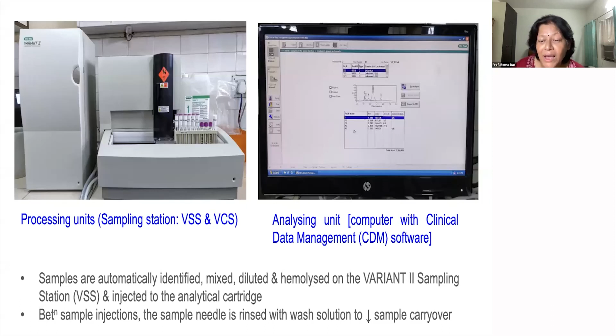Now, what are the guidelines for the interpretation of the results? You have to observe the following guidelines to assure acceptable results. The Variant 2 must pass calibration, and I'll show you the picture of how calibration looks. The retention time for the hemoglobin A2 in the calibrator is between 3.65 plus minus 0.1. This is a very specific retention time which has been given. The two major important components that we are looking at in the HPLC are the hemoglobin A2 percentage and the fetal hemoglobin percentage, right? And these are the calibration factors which we have to adhere to.